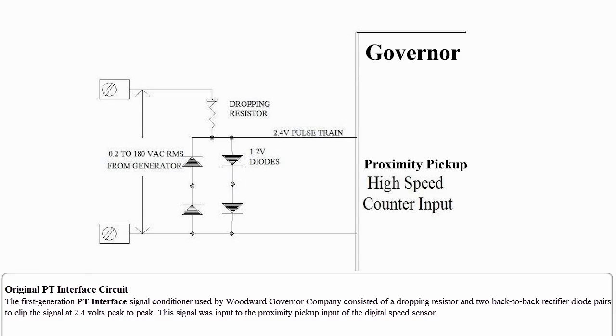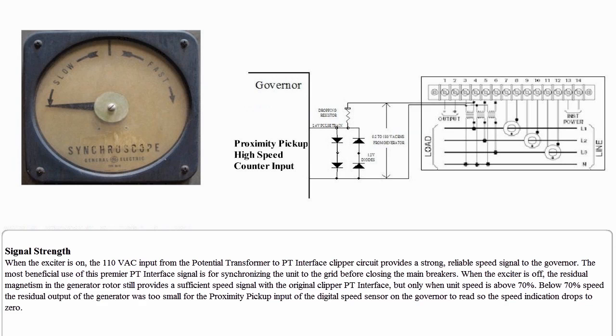The first generation PT interface signal conditioner used by Woodward Governor Company consisted of a dropping resistor and two back-to-back rectifier diode pairs to clip the signal at 2.4 volts peak to peak. This signal was input to the proximity pickup input of the digital speed sensor. When the exciter is on, the 110 volt AC input from the potential transformer to the PT interface clipper circuit provides a strong, reliable speed signal to the governor.